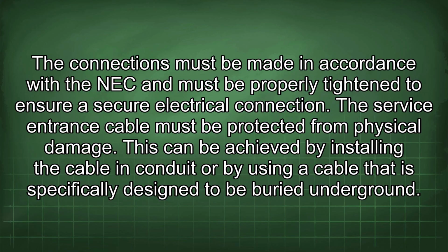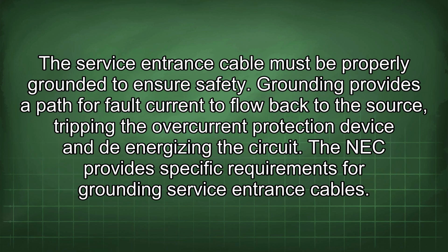This can be achieved by installing the cable in conduit or by using a cable that is specifically designed to be buried underground. The service entrance cable must be properly grounded to ensure safety. Grounding provides a path for fault current to flow back to the source, tripping the overcurrent protection device and de-energizing the circuit. The NEC provides specific requirements for grounding service entrance cables.